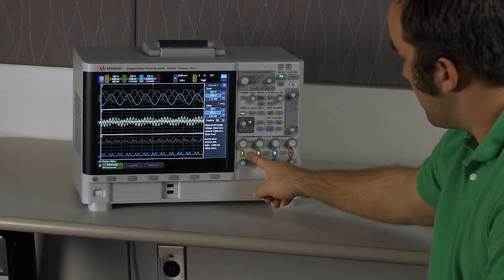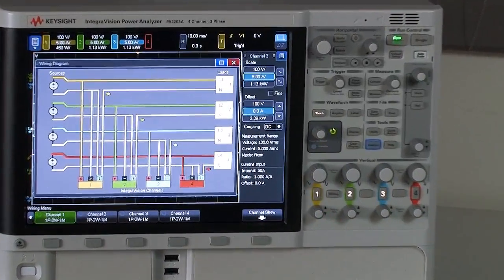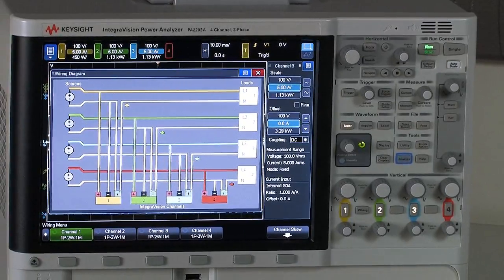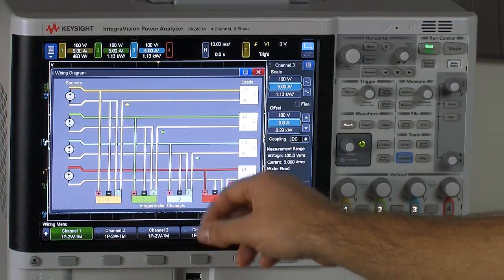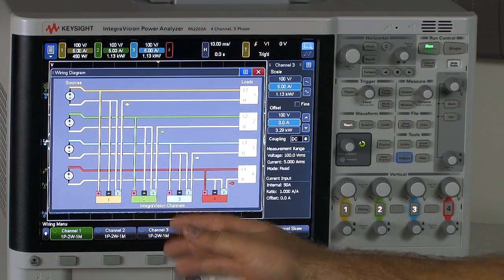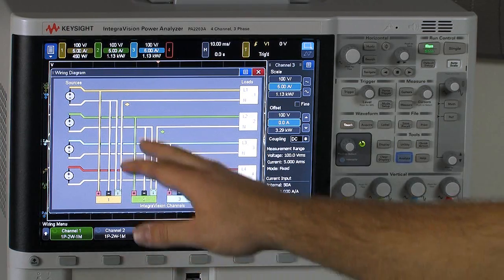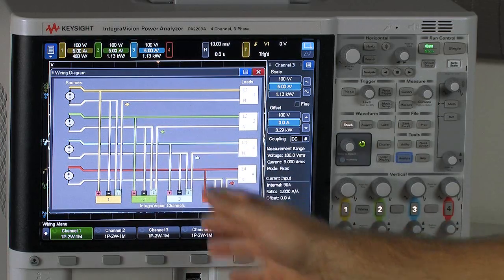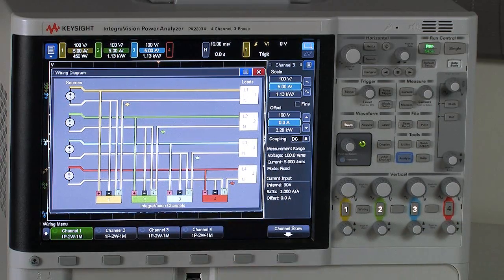To start off, I'm just going to go right over here and hit our wiring hard key. What you're going to see, this is going to bring up our wiring diagram. So as you can see, in the default state of the instrument, each of the four input power channels on the PA2203A are set up to be for individual measurements. They're completely separate. They're not grouped together.